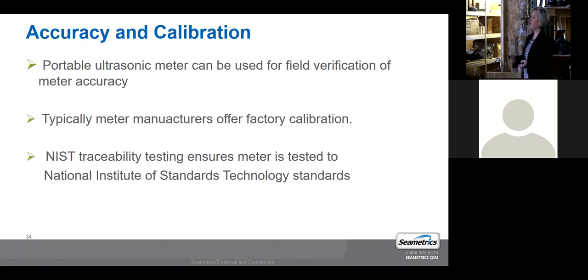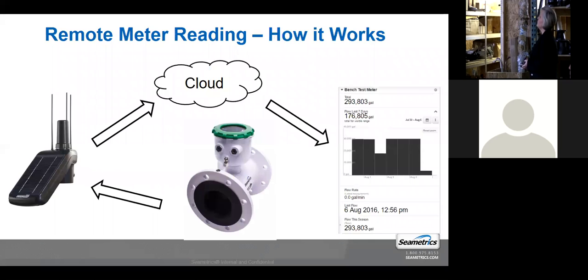Otherwise, if it's acceptable, there's portable devices. This isn't the only one. There's a lot of manufacturers that make portable ultrasonic meters to test the accuracy, used as a verification device. Remote meter reading, AMR, automatic meter reading, has been around many, many years with housing meters. Probably most of us, that's how our meters have been read for a number of years. It is now becoming more and more common in the world of irrigation. It's being referred to right now as remote meter reading.